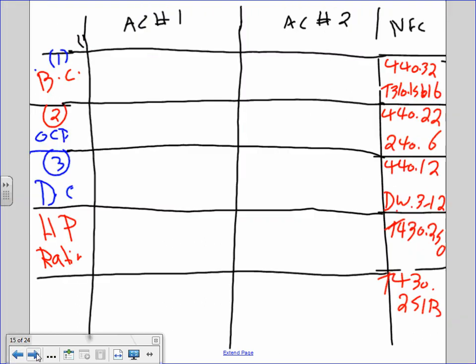Per 440.32, you multiply the full load amp by 1.25. So for chiller one: 1.25 × 70 = 88 amps. For chiller two: 1.25 × 120 = 150 amps.